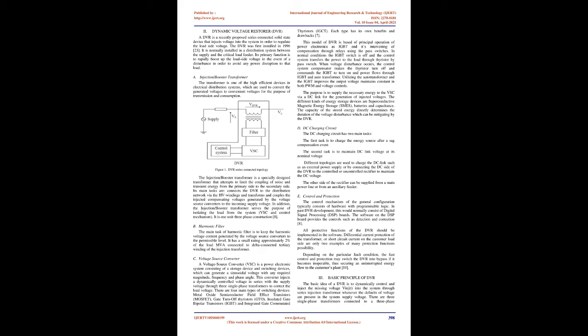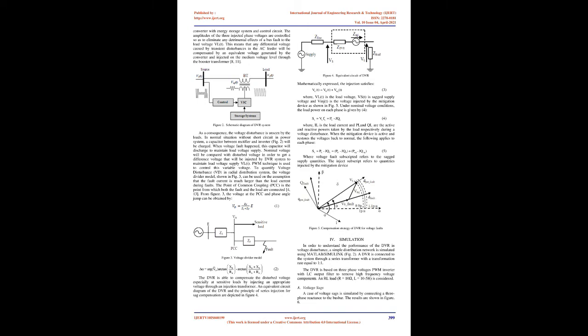Harmonic filter. The main task of the harmonic filter is to keep the harmonic voltage content generated by the voltage source converters to the permissible level. It has a small rating, approximately 2% of the load MVA, connected to the delta connected tertiary winding of the injection transformer.